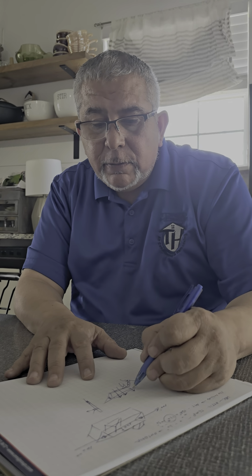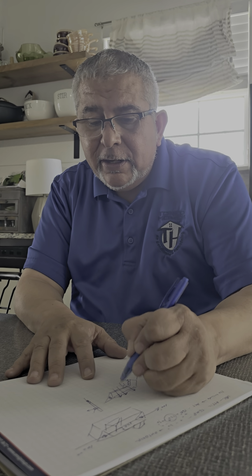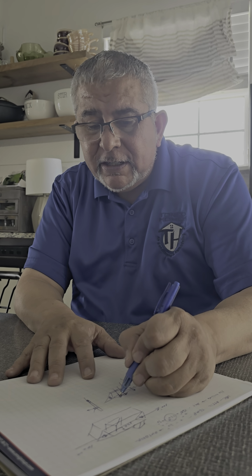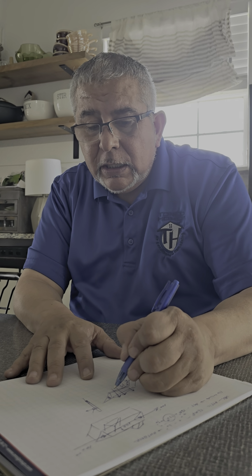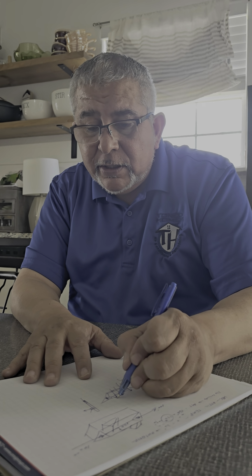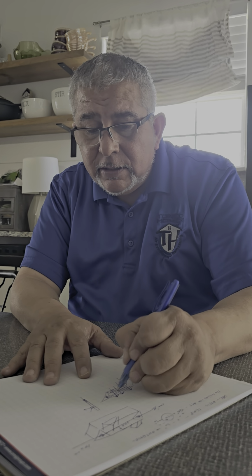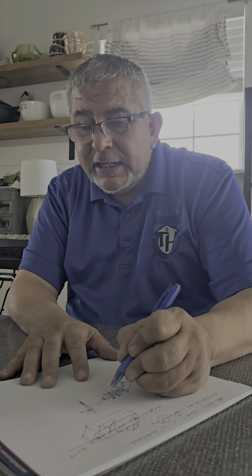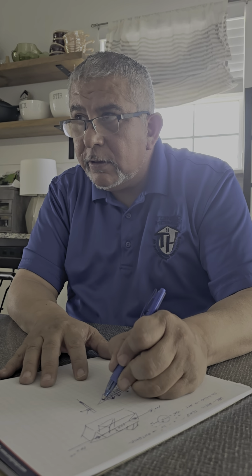Makes sense. So when the house has a gable vent, the air doesn't come from the soffit to the gable. I mean, excuse me, if you have a ridge vent on top and soffit vent on the bottom, but you have a hole on the side, the air only goes like this. So all this area will not get any air, even though you have this vent on top. It's going to pull the air from the closest hole.